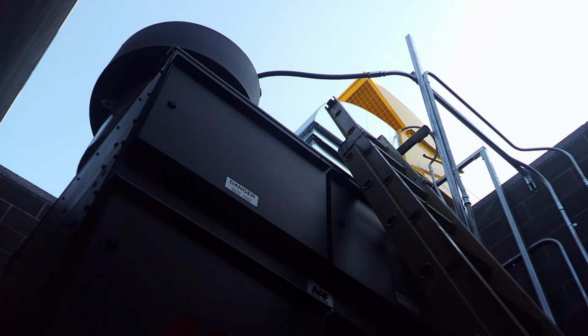That's why the VFD, in my opinion, has turned out to be a good thing. It's probably cheaper in the long run to put that VFD in there than have a balancer spend 4 or 5 hours taking bearings, pulleys off, testing it, putting a new pulley on, and fooling with it. That could be a whole day. This is 5 minutes.